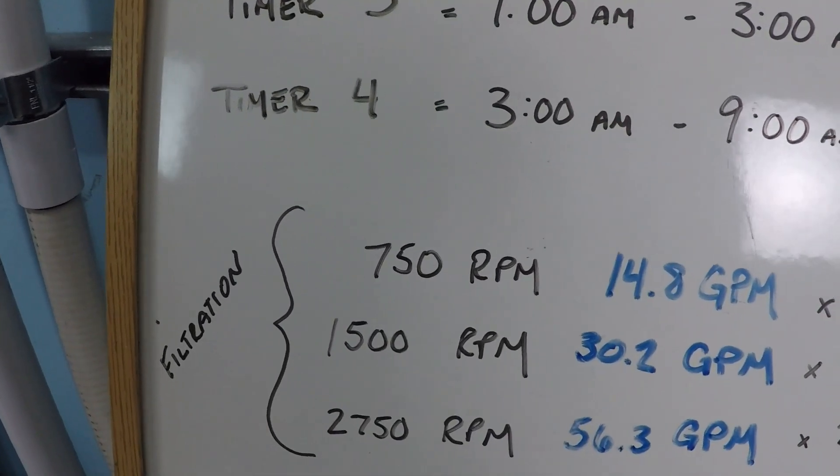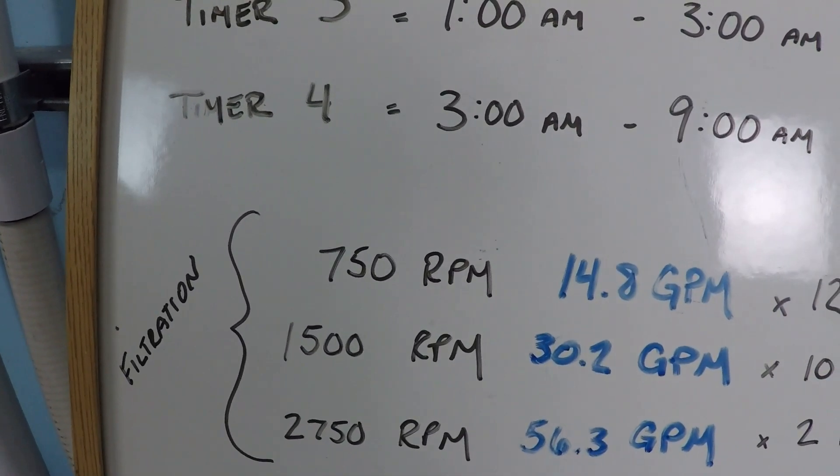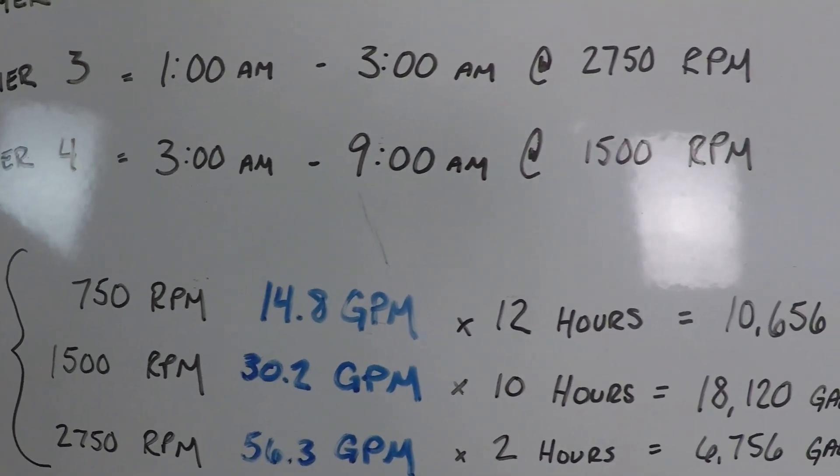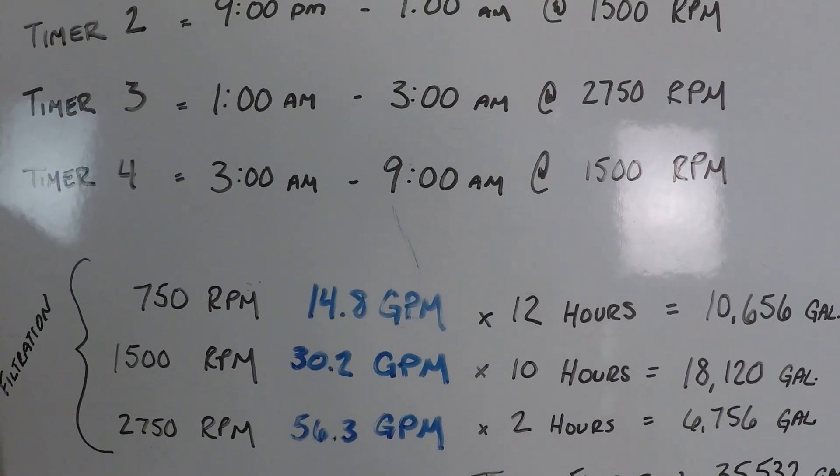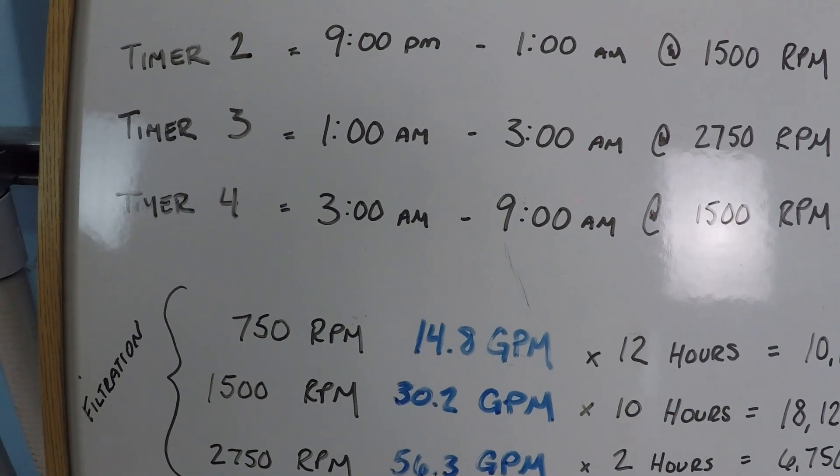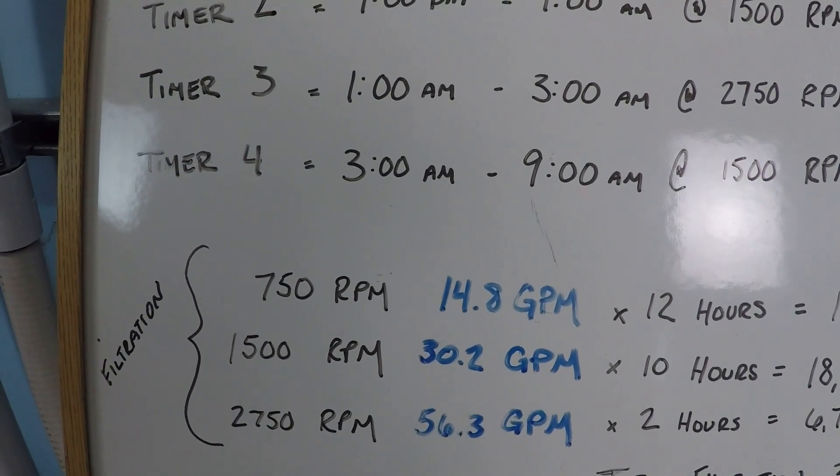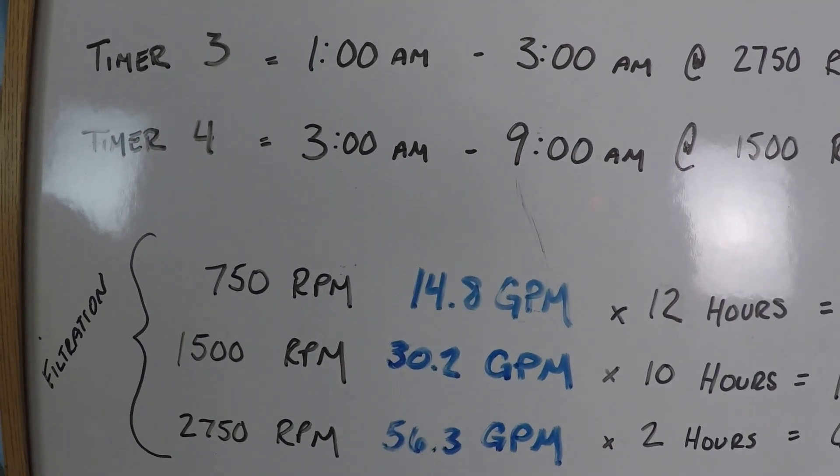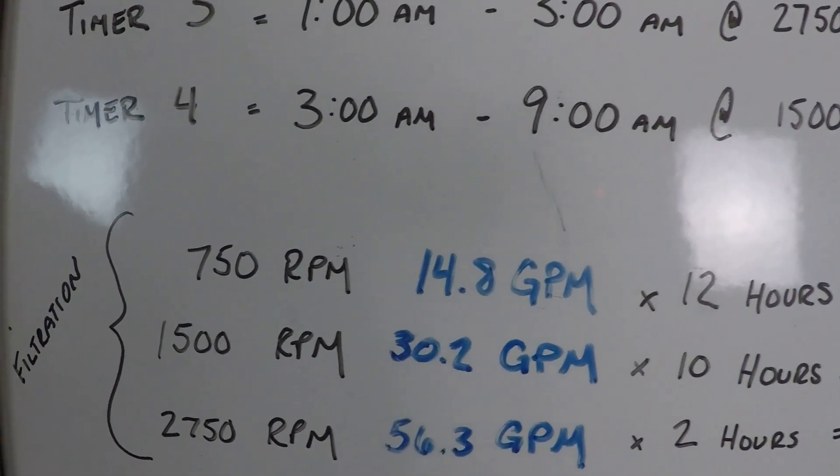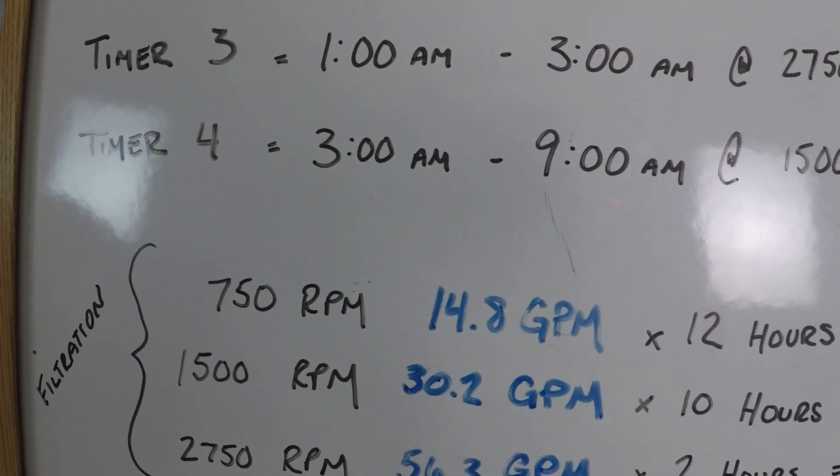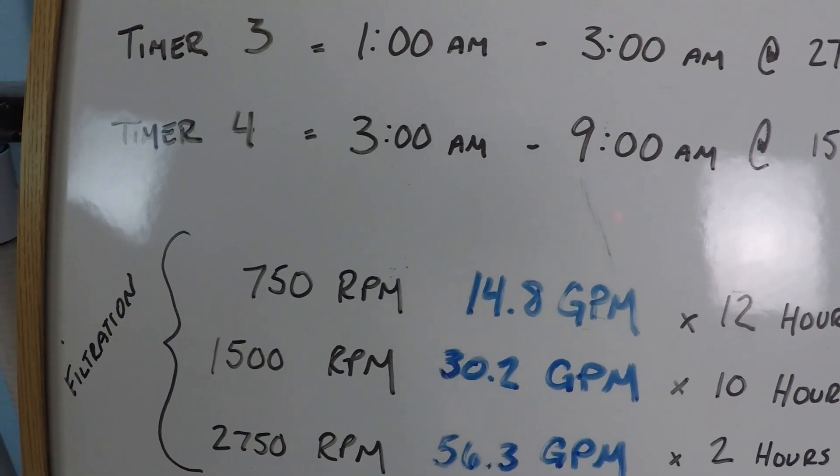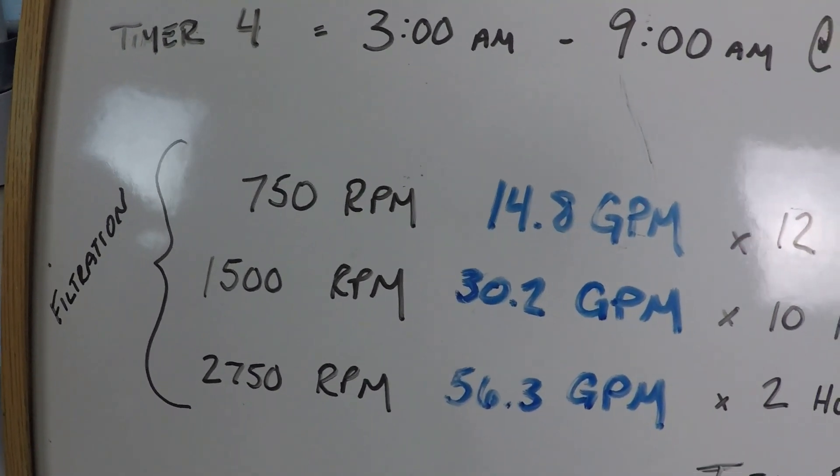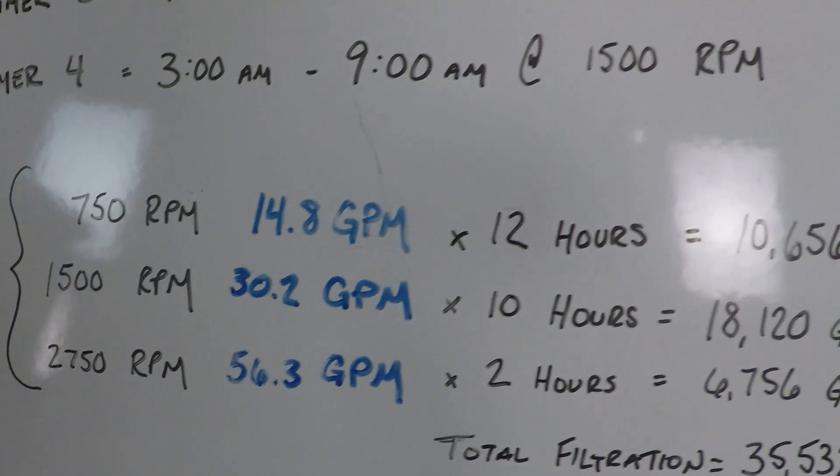Now, what I'm going to show you next is the amount of flow that you can get for these different rpm values. It is very significant to note that every swimming pool system is unique. This is what my system gets. Your system will get different values. But this gives us a starting point for comparison. So, as you can see, at 750, we're at just under 15 gallons per minute. 1500 is about 30 gallons per minute. And 2750 is about 56 gallons per minute.